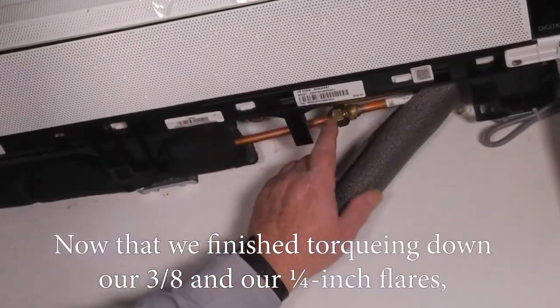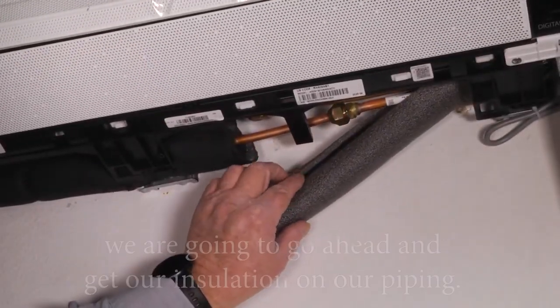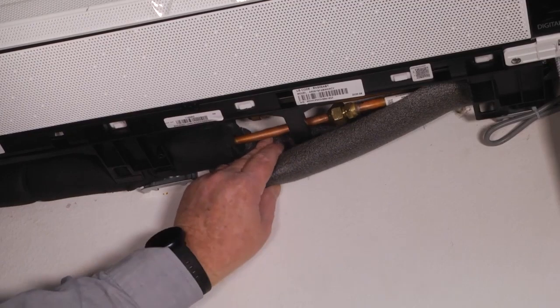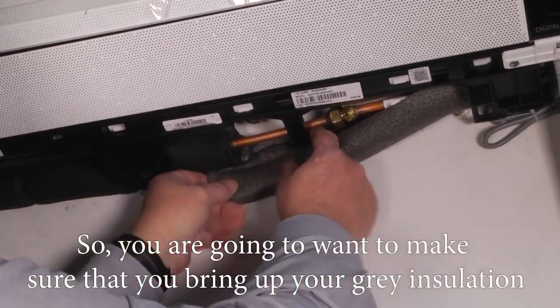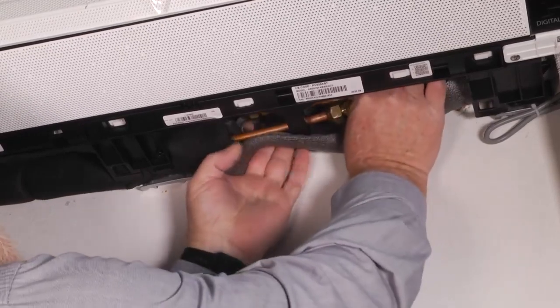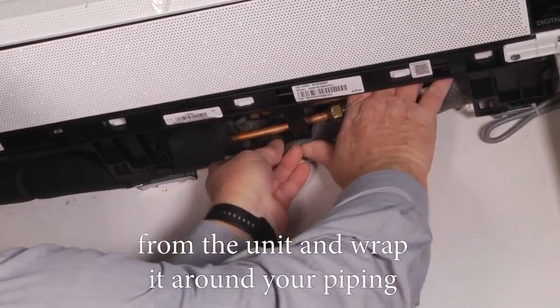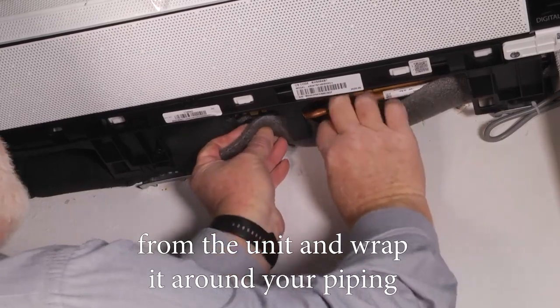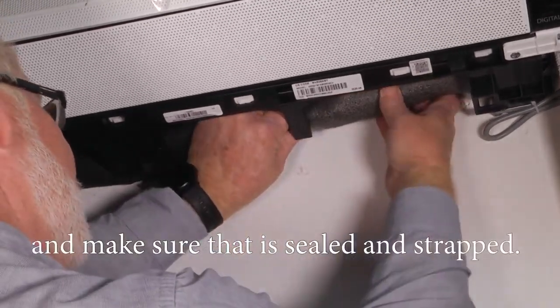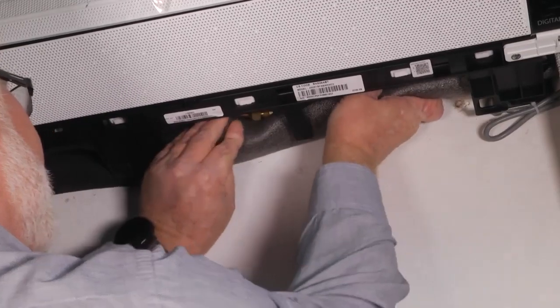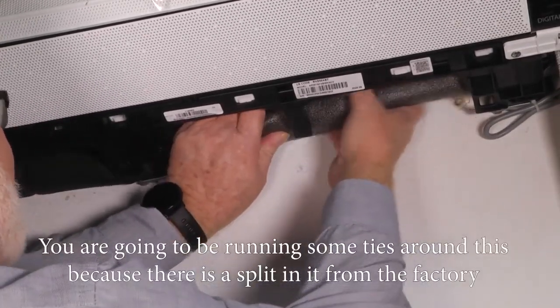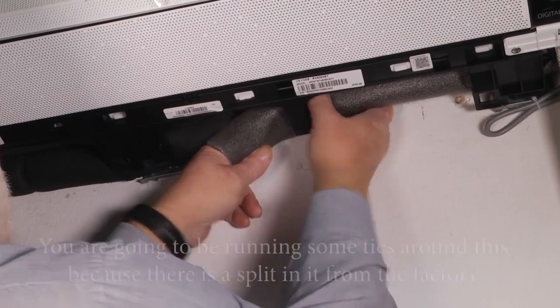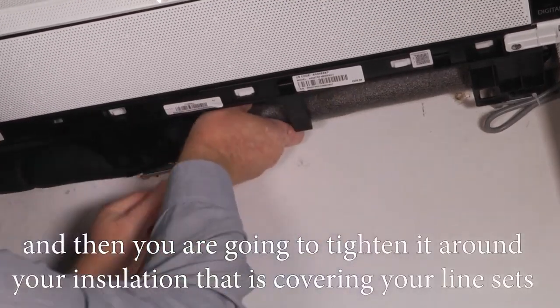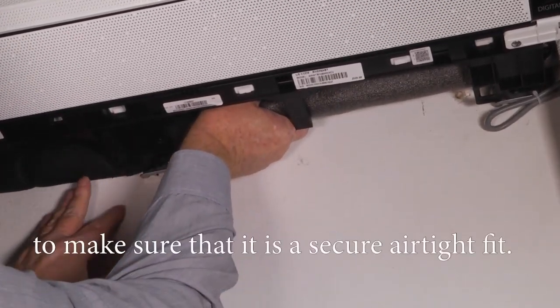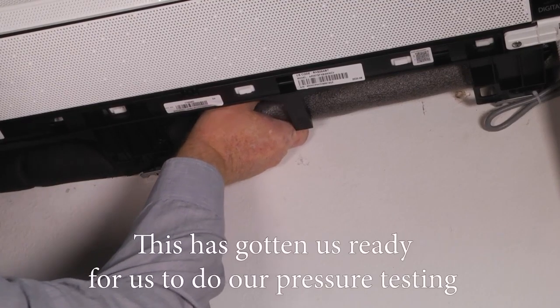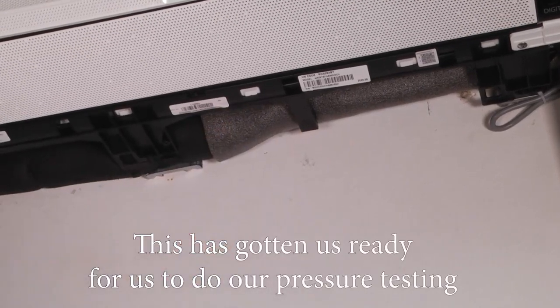Now that we've finished torquing down our 3/8 and our 1/4 inch flares, we're going to go ahead and get our insulation on our piping. So you're going to want to make sure that you bring up your gray insulation from the unit and wrap it around your piping and make sure that it's sealed and strapped. You're going to be running some ties around this because there is a split in it from the factory. And then you're going to tighten it around your insulation that's coming on your line sets to make sure it's a secure, airtight fit. And then this has gotten us ready to do our pressure testing and evacuation.